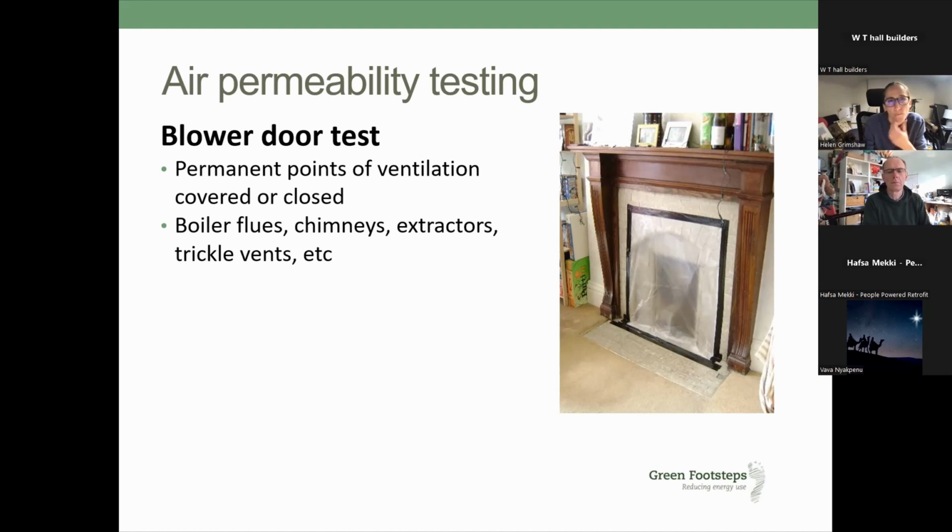They need to understand that those open fires are going to significantly impact the energy use of the building in real life, but they're excluded from the air permeability test. So you need to bear that in mind, and when we're talking about things on a holistic basis with a client, that needs to be emphasized.